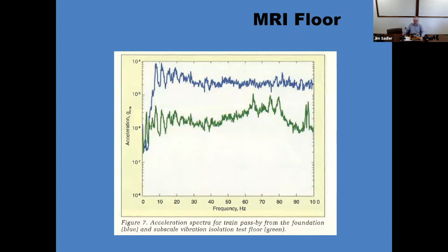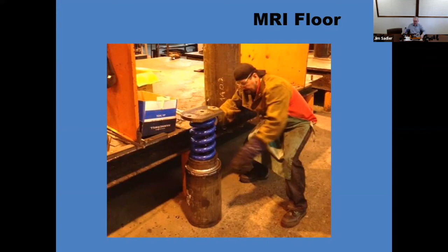This is just a construction of that mount. The reason we needed that depth and weight for that MRI system is we wanted to reduce the ring time. So when a patient walked in to get into the MRI, the floor would move a little bit - not perceptible to the patient, but it would blur the image. So the idea was to create this big mass to reduce how long that would oscillate.